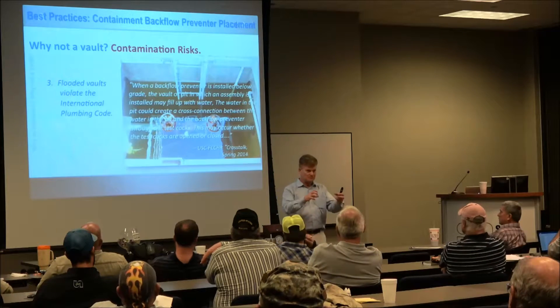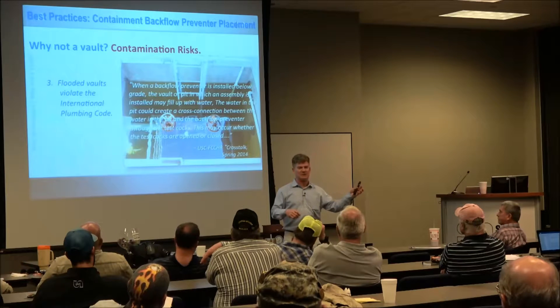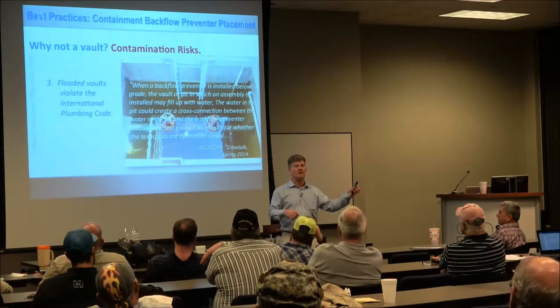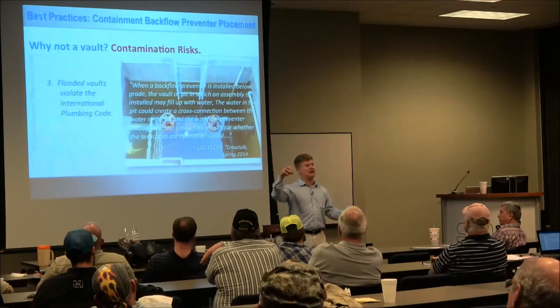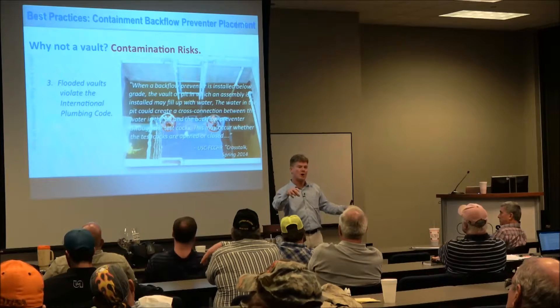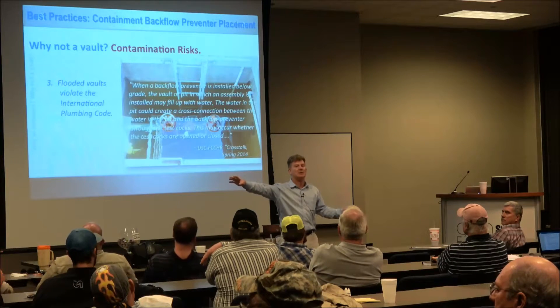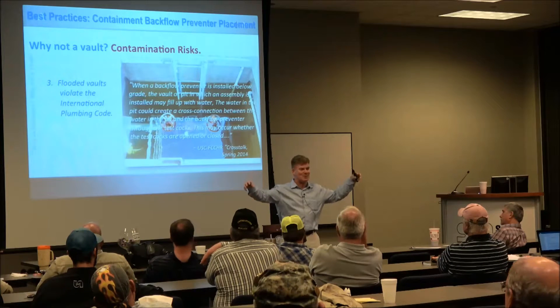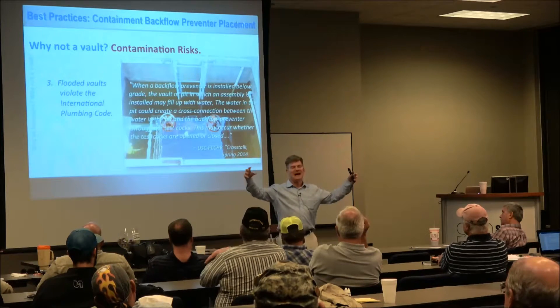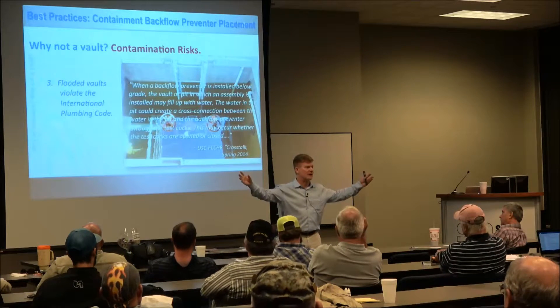How is that possible? Aspiration. If you have a test cock on number one that's leaky even when it's closed, every time you have a backflow event you're pushing contaminated water from that vault into the city water main. And every time you have the same kind of valve on number four, you're pushing vault water into the customer's water continuously. There's no protection on test cock number one or test cock number four — all that expensive backflow assembly science, and yet no protection at the outer ends.